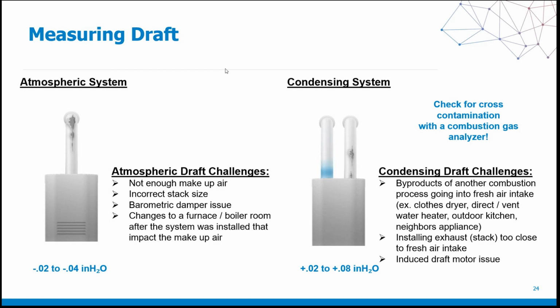And one of the last things is that if a homeowner or business owner has changed the layout of the furnace or boiler room, and by that I mean if there was once a louvered door there, because that's what the room called for to provide it with enough makeup air, and if someone has replaced that louvered door with a solid core door, you're not getting the same amount of airflow going to that system, because that solid core door is blocking it, because there are no louvers to allow airflow in.